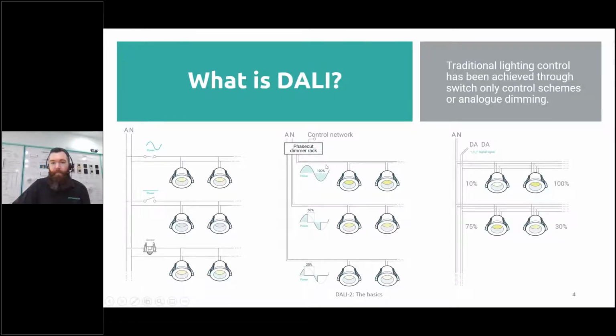The other issue is, of course, that phase dimming worked fairly well for incandescent lights, averagely for CFLs, and very poorly for any LEDs. To this day, it is still very difficult to get a good quality, consistent, flicker-free dimming with your traditional phase cut style dimmers. So that's why we were looking at these digital technologies.